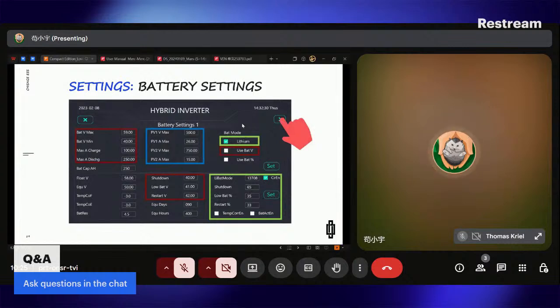Here, we can see different battery modes. It has lithium, battery voltage, and battery percentage mode. Lithium is when you have BMS, you always need to choose the first one. And if you do not have BMS, you can use the second one or third one. And for the battery percentage mode, it's still similar to the voltage mode. Just the inverter will try to use the voltage to calculate the SOC, but it cannot be very accurate. So it's still recommended to use the voltage mode.